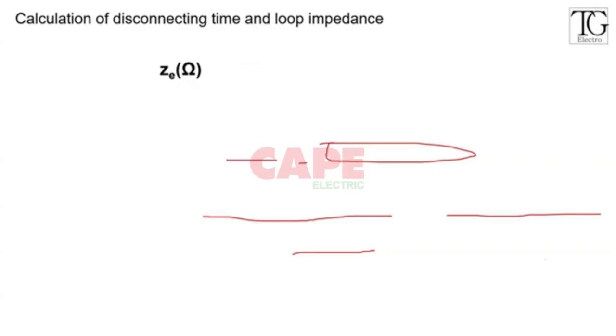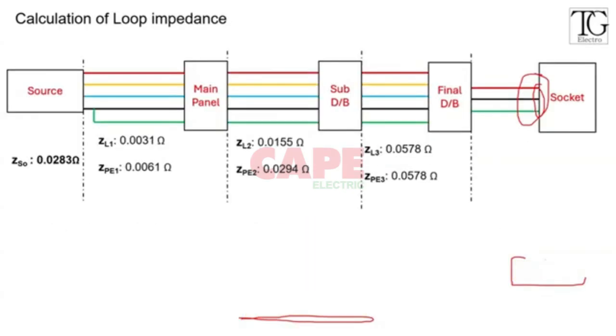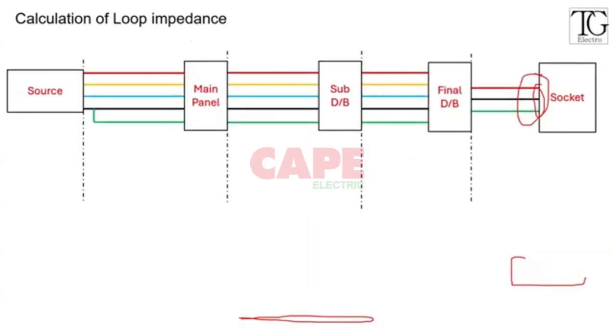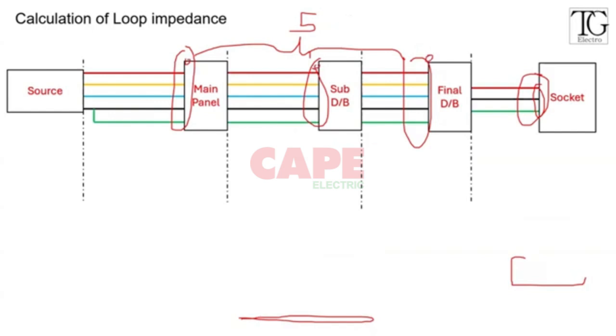I'll just explain this. Give me a minute. So in this, if I take this DB, or this DB, or this DB, it is all going to be 5 seconds. Why have they put 5 seconds? That is due to selectivity, so that if this DB trips, this one should not trip, or this one should not trip. So they have put a maximum disconnection time of 5 seconds. But for this single phase socket, it is going to be 0.2 seconds.